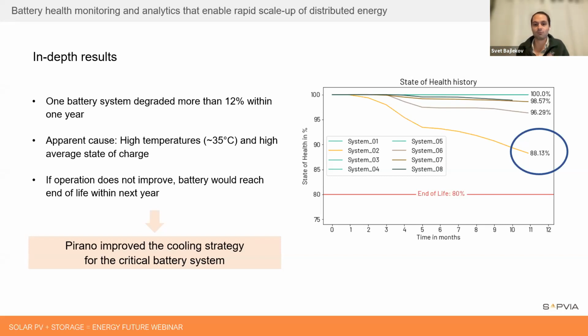We looked at what was causing this, and found that this system was operated at fairly high temperatures, usually around 35 degrees Celsius, and also a fairly high average state of charge. It spent, if I remember correctly, something like 90% of its life at a state of charge above 95%, which again is something we know theoretically accelerates aging. If the operation doesn't improve, this battery would be reaching end of life within the next year or so. If you installed this battery just 2 years ago expecting 7 to maybe even 10 years of life, that's a surprise, and it doesn't reflect well on your commercials for that project.